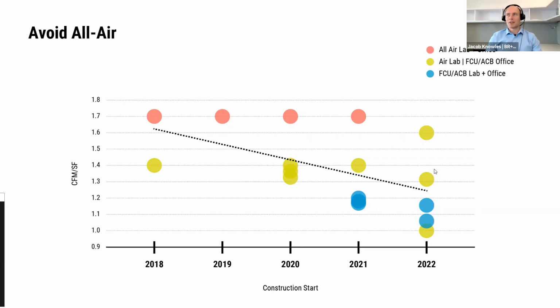The yellow ones are all-air in the lab, which is typically 2 CFM per square foot, with fan coil units or chilled beams in the office areas, typically around a 60-40 split between lab and office. The blue ones are where we've finally convinced the brokers and developers that we can do fan coil units or chilled beams in both the lab and office and reduce the CFM in the lab, in many cases, down to about 1.5, which still is a lot more than 6 air changes, but it's better.